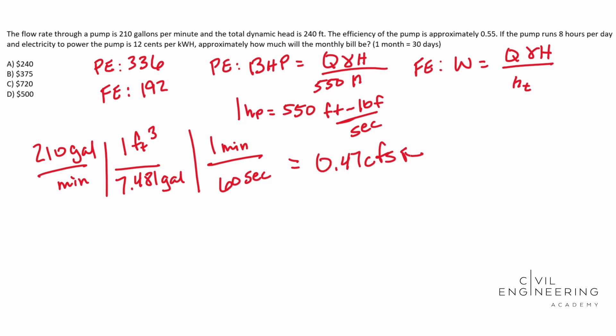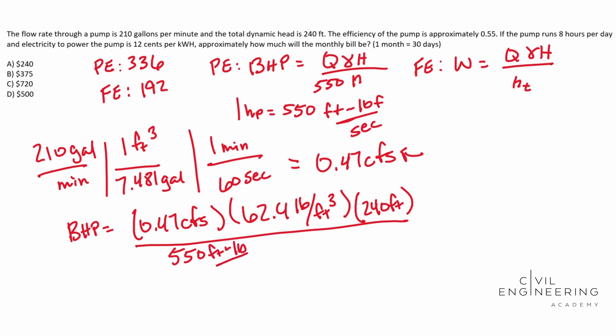So let's plug all that into our BHP formula here. So BHP is equal to our flow rate 0.47 cubic feet per second times our gamma. Let's assume water, it doesn't specify, 62.4 pounds per cubic foot. And then we need to multiply that by our head. Our head is given in the problem as 240 feet. And we're going to put all that over 550 foot pounds per second. And then we need to multiply that by, always remember to write out your units so that way you can make sure they work out.